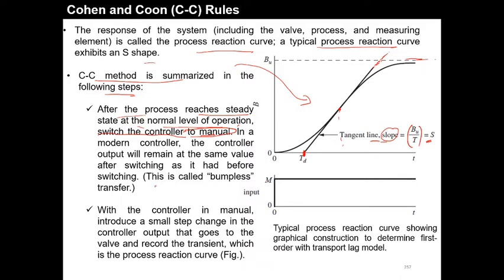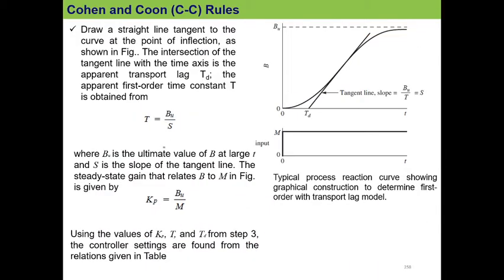In a modern controller, the controller output will remain at the same value after switching as it had before switching. With the controller in manual, introduce a small step change of amplitude m to the controller output that goes to the valve, and record the process reaction curve. Once the reaction is achieved, you can find out the time delay td. Draw the tangent to the curve at the point of inflection — the intersection of the tangent line with the time axis gives the apparent transport lag td.